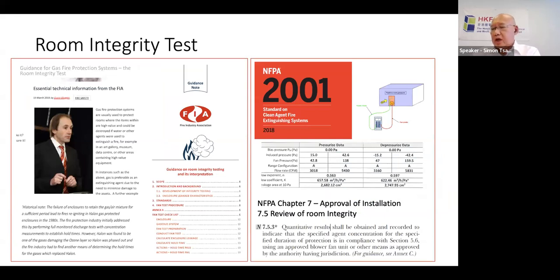Carbon dioxide, halon, clean agent, and inert gas extinguishing systems are commonly adopted in Hong Kong for facilities such as data centers, switch rooms, or other electrical hazardous areas. The effectiveness of the extinguishing system depends very much on the concentration of the extinguishing media and the hold time provided. In March 2019, Mr. Andrew Ender, chairman of the Working Group Gas, Fire Industry Association, FIA, stated that the overall integrity of the system is vital. Many factors contribute greatly to the overall effectiveness of the system, including the design of the system, the quality of the installation, the testing of the pipes that carry the gas, and the integrity of the protected rooms.